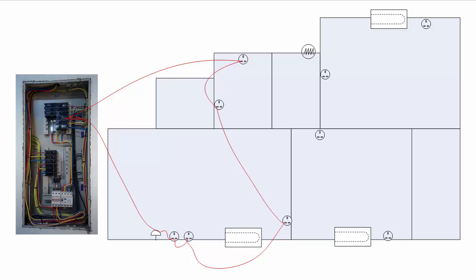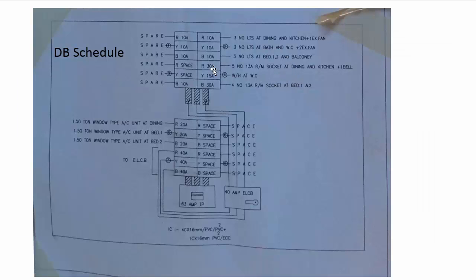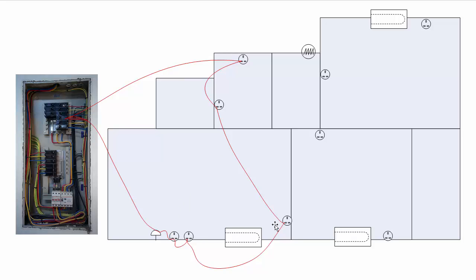The 30 ampere MCB is used to supply five 13 ampere ring main sockets at dining and kitchen, including the bell. So these are the five socket outlets in the hall and kitchen, and the ring also includes the bell. The connection starts from the 30 ampere MCB, goes to the line terminal of the bell, then to the first socket, second socket, third, fourth, fifth, and finally comes back to the same terminal on the MCB to complete the ring.